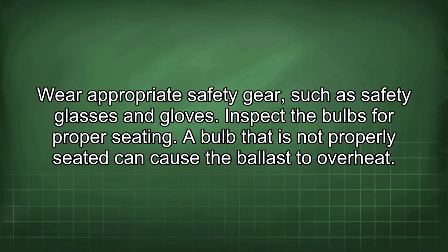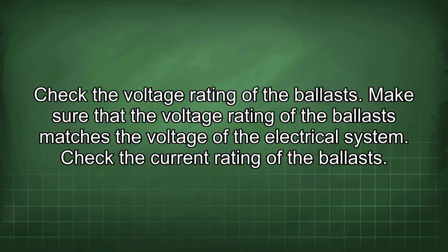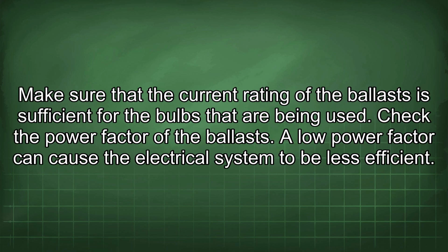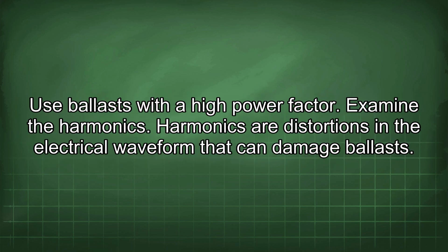Inspect the bulbs for proper seating. A bulb that is not properly seated can cause the ballast to overheat. Check the voltage rating of the ballasts. Make sure that the voltage rating of the ballast matches the voltage of the electrical system. Check the current rating of the ballasts. Make sure that the current rating of the ballast is sufficient for the bulbs that are being used. Check the power factor of the ballasts. A low power factor can cause the electrical system to be less efficient. Use ballasts with a high power factor.